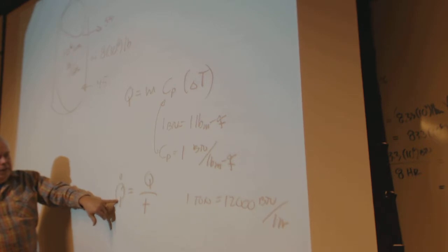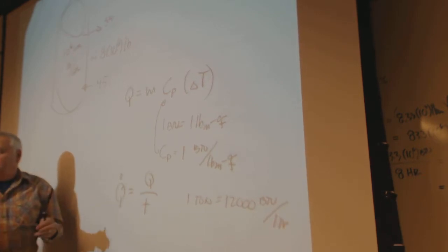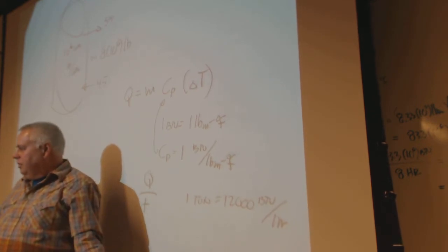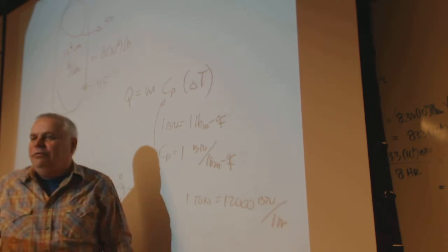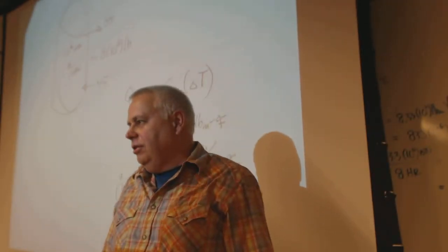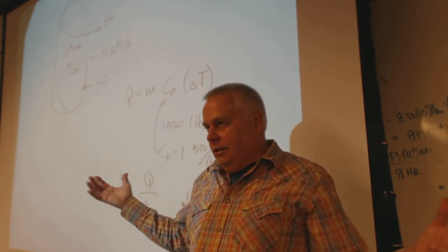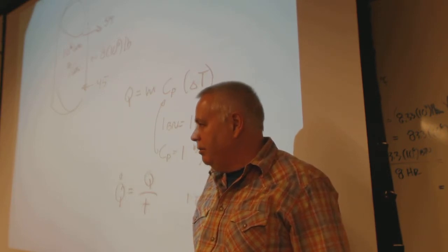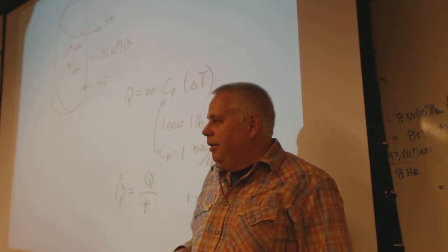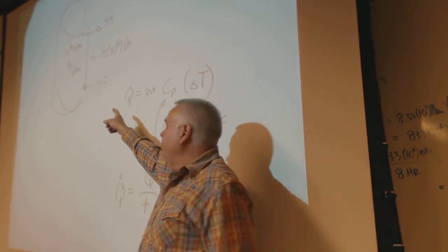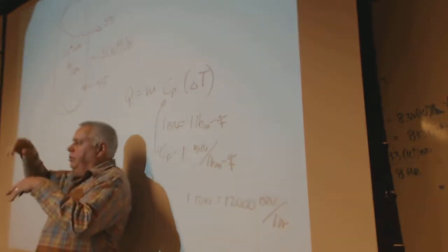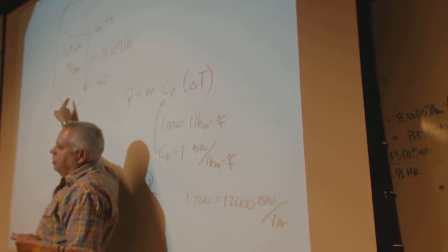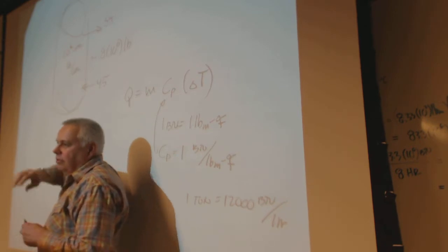And the rate at which you could discharge if you did it over the course of an 8-hour day. You charge it up at night. We have these coolers that have 4,000 volt, 3-phase motors turning a turbine at multiple tens of thousands of RPM, and there's energy it takes to do that, pumping the refrigerant, compressing it. You can charge this tank at night just by running through the cooler that's not part of the refrigerant thing, and basically charge this up for free without the electricity of the compressor.